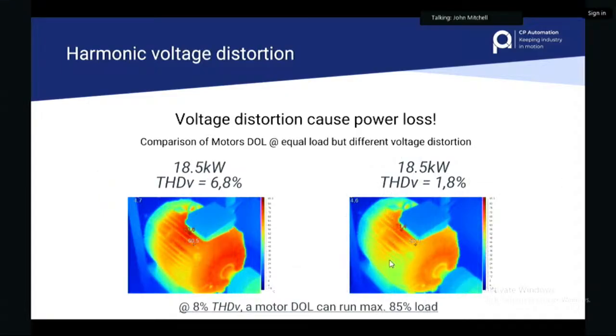Another thing people aren't aware of is voltage distortion, which is caused by the current distortion into the transformer, and can make direct online motors inefficient. And if you see there at the bottom, if you had a voltage distortion of 8%, which is kind of the limit that the standards dictate these days, a DOL motor can run only to a maximum of 85% of its load. So you've derated your on-site motor's power by 15% by not fixing the current harmonics going to the transformer.